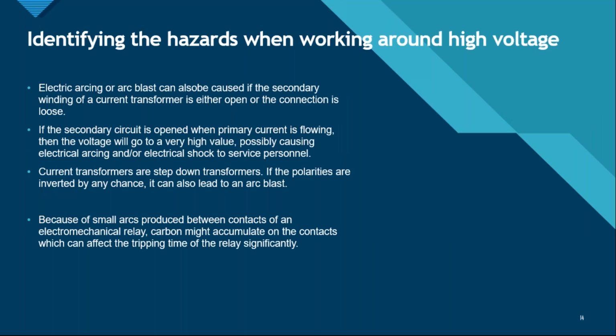Electrical arcing or arc blast can also be caused if the secondary winding of a current transformer is either open or the connection is loose. If the secondary winding is open, because the circuit is open, high voltage might be generated on the secondary winding of the current transformer, and that can cause another case of electrical arcing or electrical shock to any service personnel.